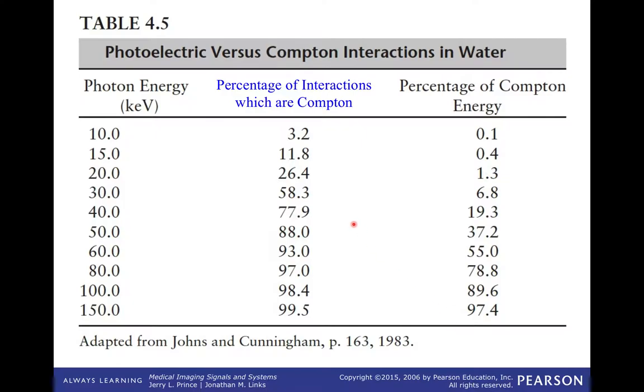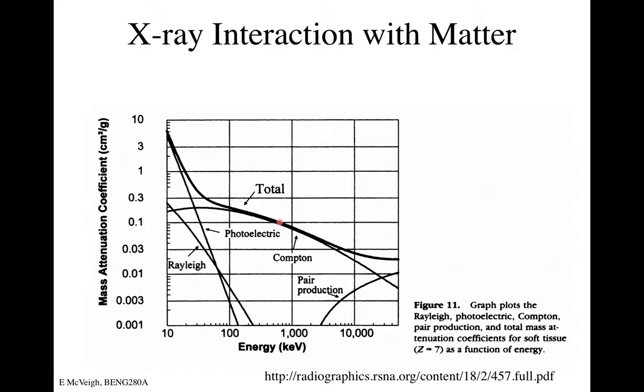Over the set of energies that might come out of our X-ray tube — say 10 keV all the way to 150 keV — as we get up to about 50–60 keV, pretty much all interactions are Compton interactions. By that energy the photoelectric effect is no longer making a significant difference.